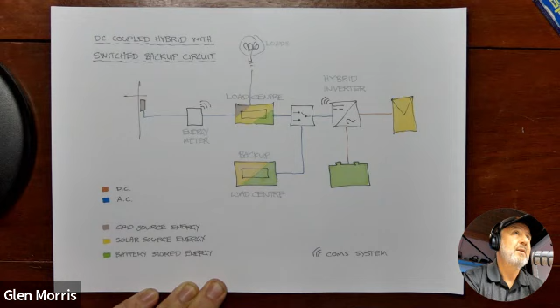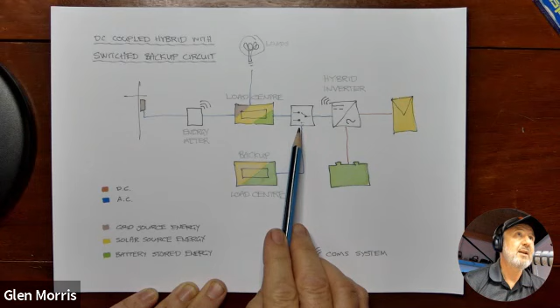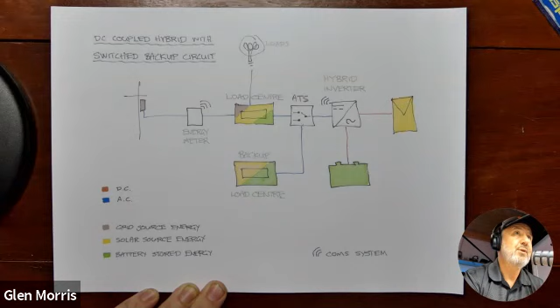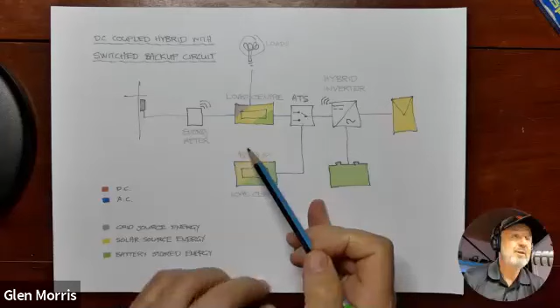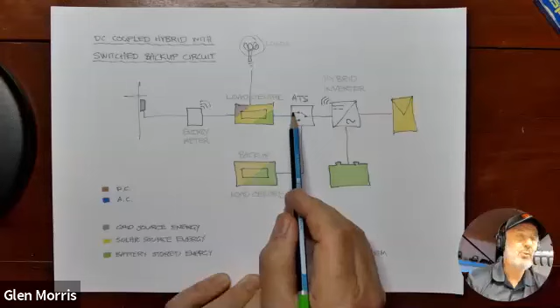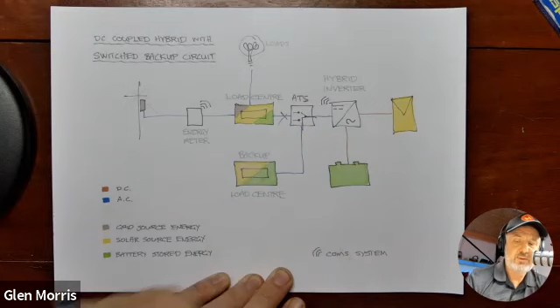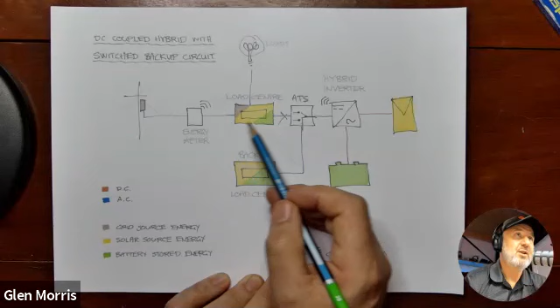But there is a way to make that work as a backup system, and that's what I've got here. You might notice it's almost the same diagram except for this device, referred to by the acronym ATS, an automatic transfer switch, which is powered by the grid. So when the grid fails over here, this switch automatically isolates this connection and connects through this other connection, allowing this inverter to carry on powering a backup circuit safely without risking trying to energize the grid when it shouldn't be energized.